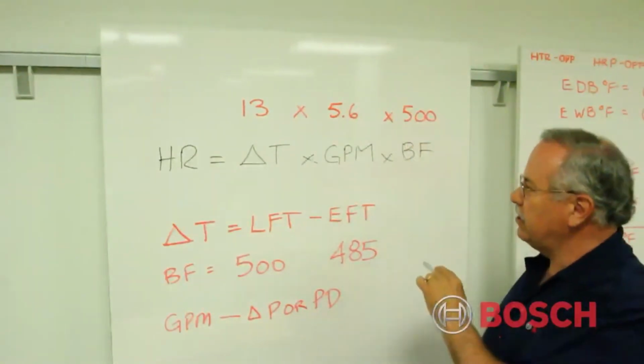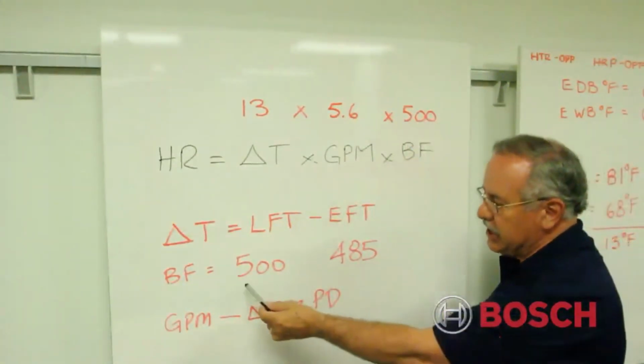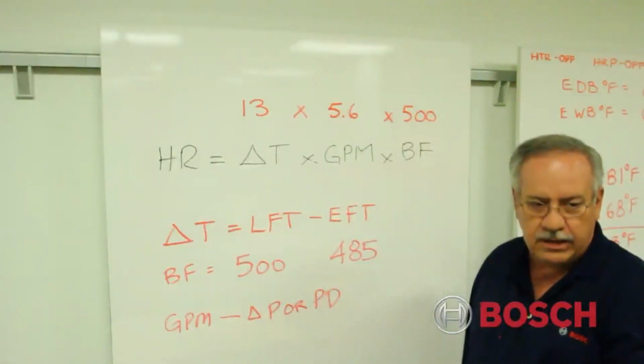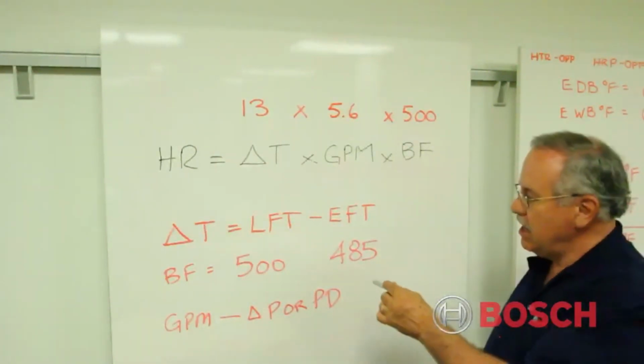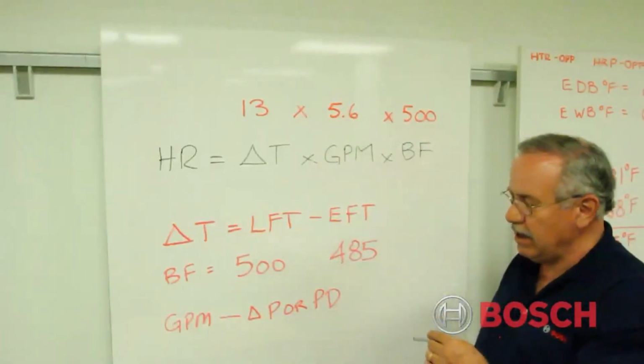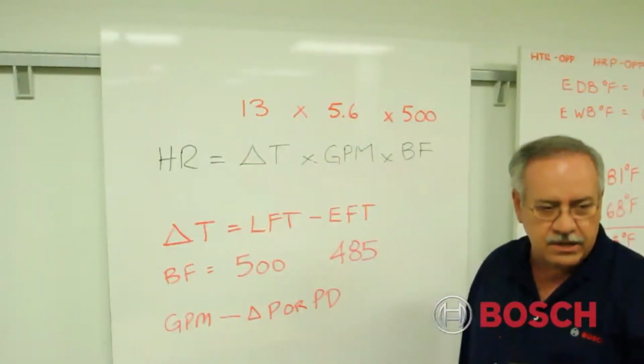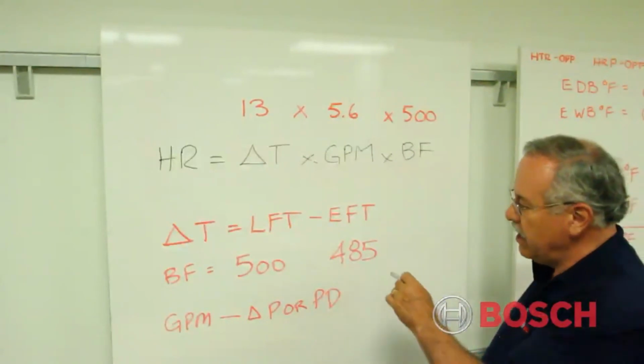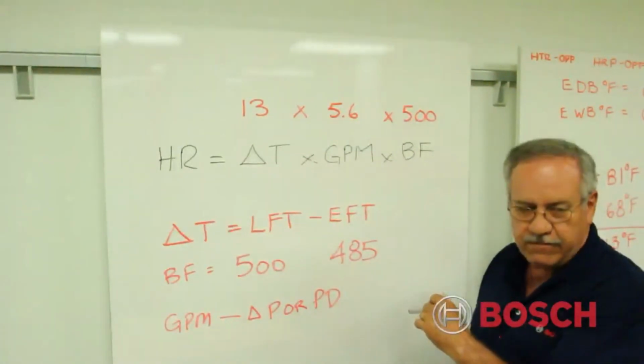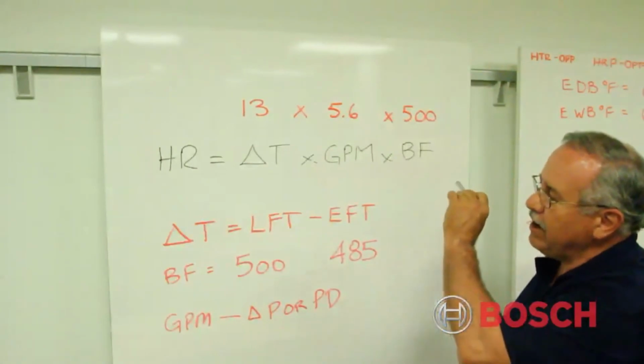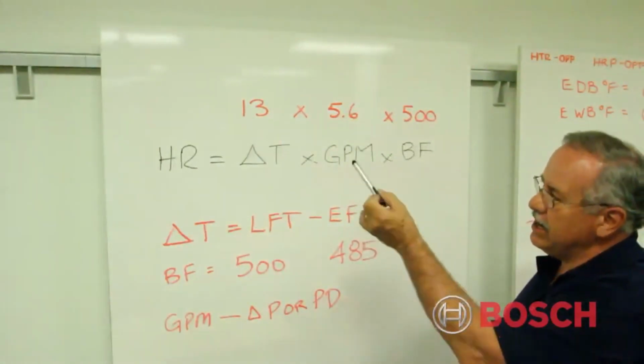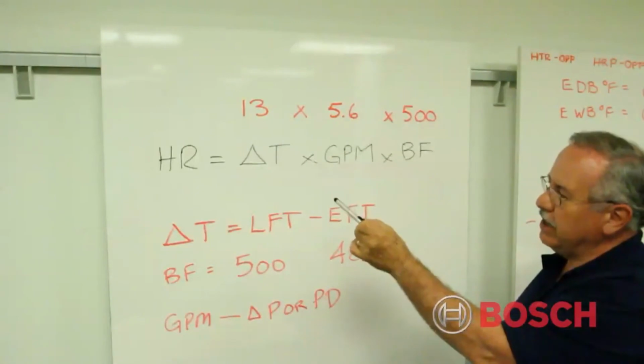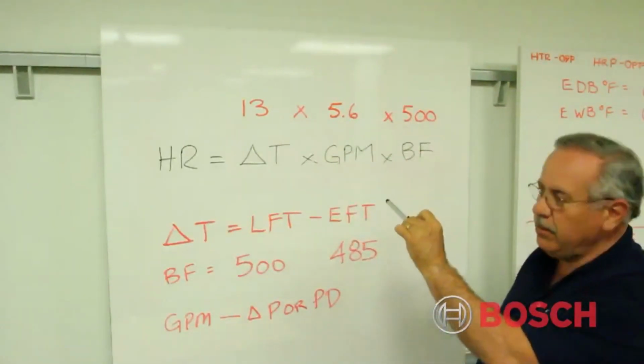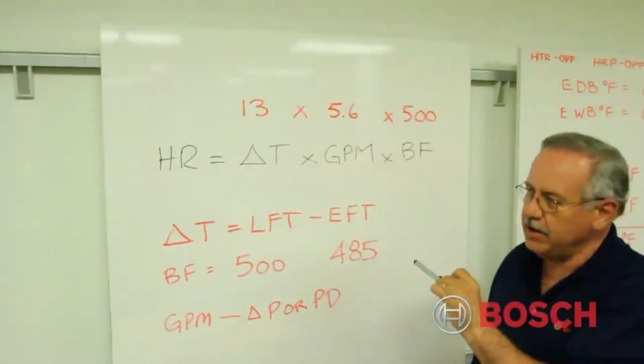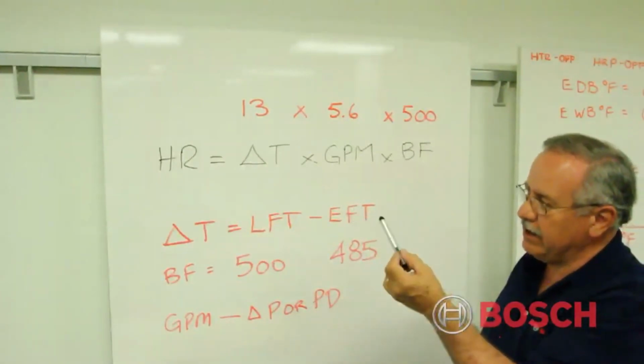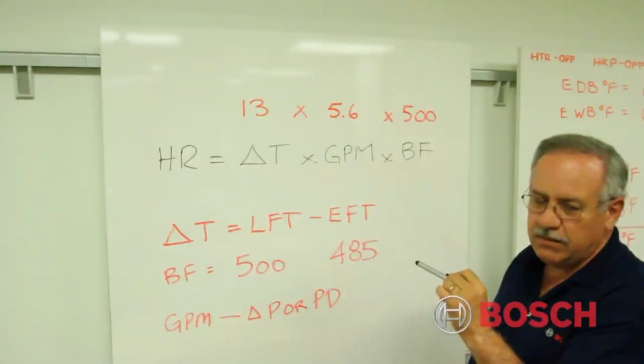He also substituted for the brine factor 500, which we said earlier was water only, and that's what we were using in this particular case. If Mark had been using a glycol, antifreeze, methanol, or any other acceptable antifreeze solution with a closed loop, then he would have simply substituted 485 into the formula.